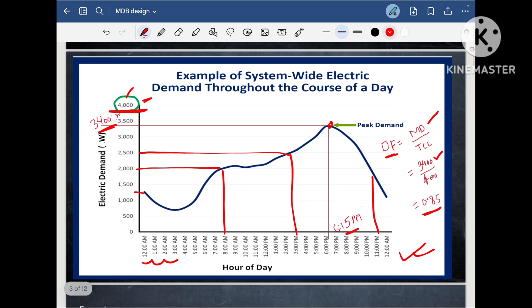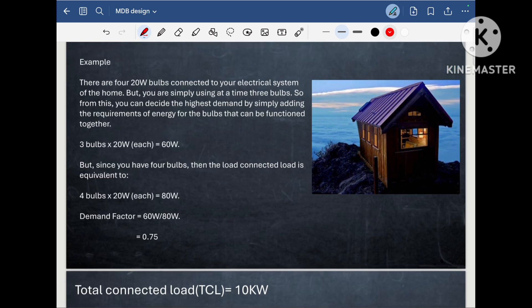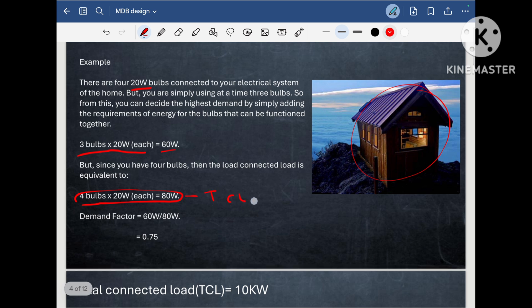I hope you understood what is maximum demand, total connected load and demand factor. Now consider there is a small security room. It has 4 bulbs and each bulb has a 20 Watt load, and at a time only 3 bulbs are working — the security guard is only turning on 3 lights. So how many lights are connected in this security room? 4 bulbs. So the total connected load is 80 Watt, and the maximum load running is 3 into 20 Watt, so 60 Watt.